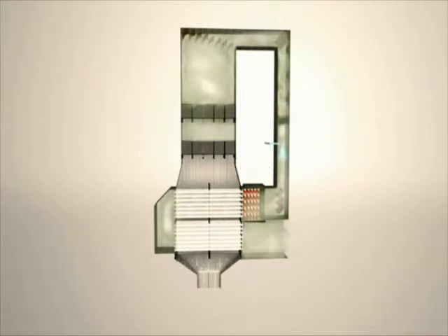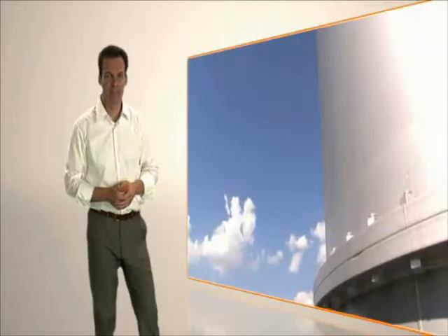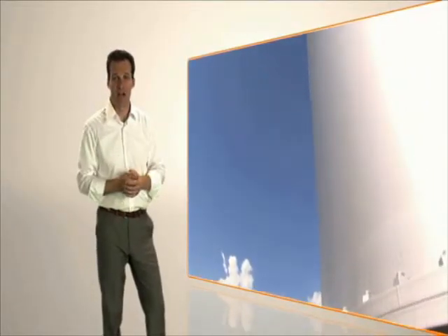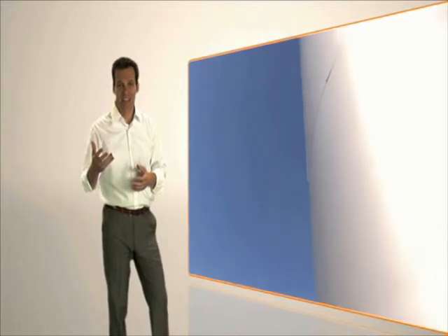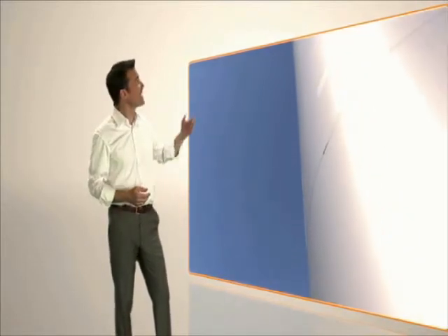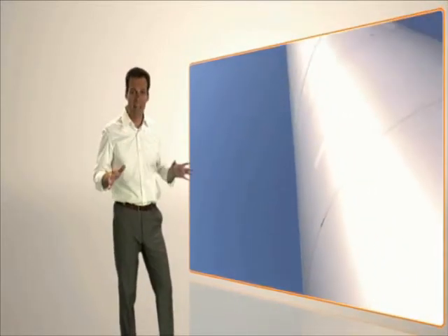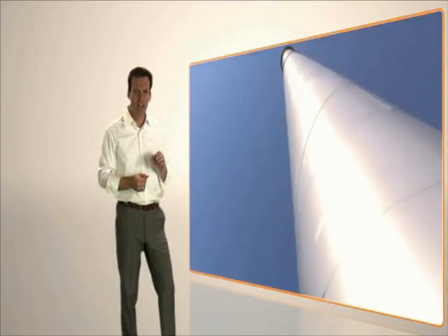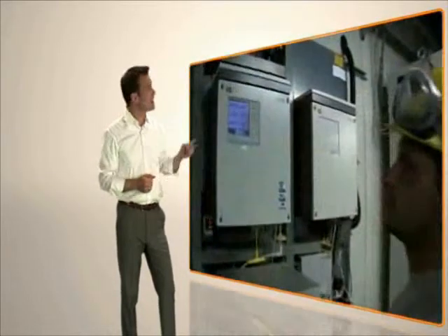These cubes, made of porous ceramic, have a multitude of thin channels through which the flue gas can flow. On the surface of the catalyzer, optimal conditions prevail for the chemical reaction that allows the mixture of nitrogen oxides and ammonia water to become harmless nitrogen and water vapor. At this stage, the flue gas cleaning is completed, and the pure gas is dispersed via the chimney at a height of 80 meters. The clean combustion air that leaves the plant is put through a stringent test.